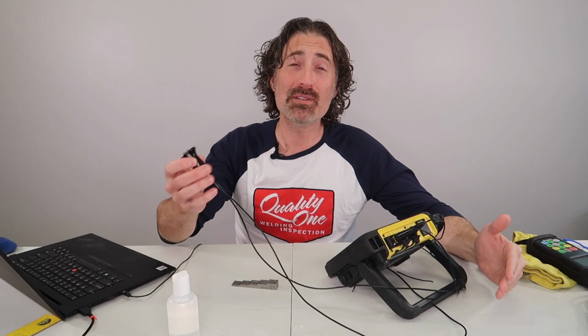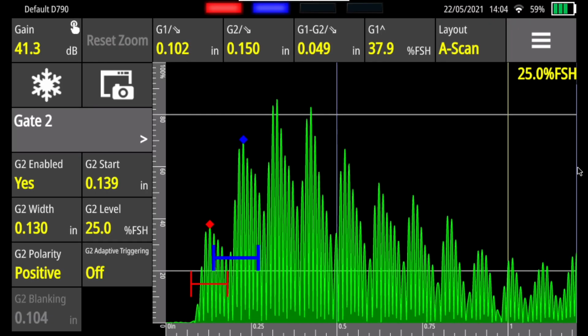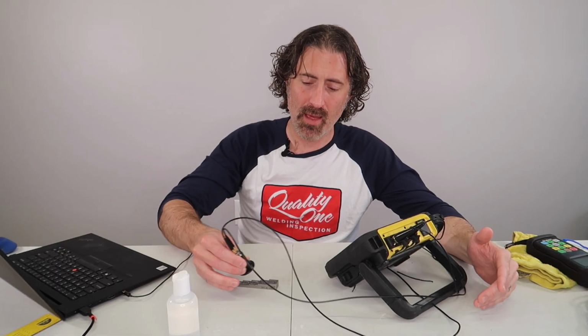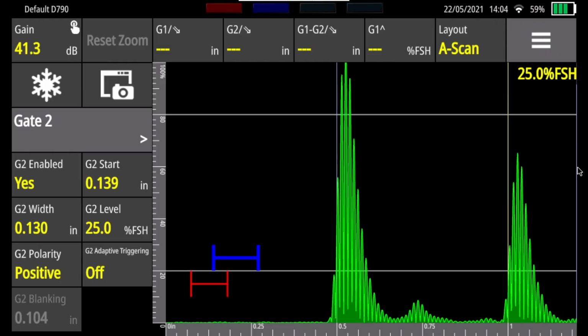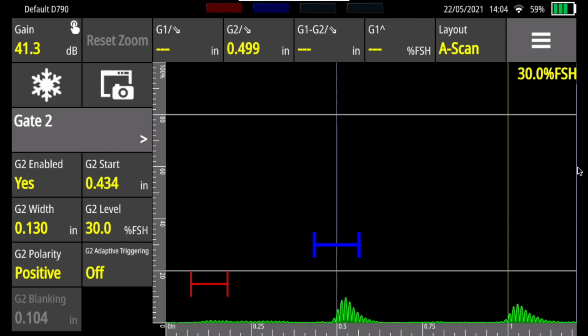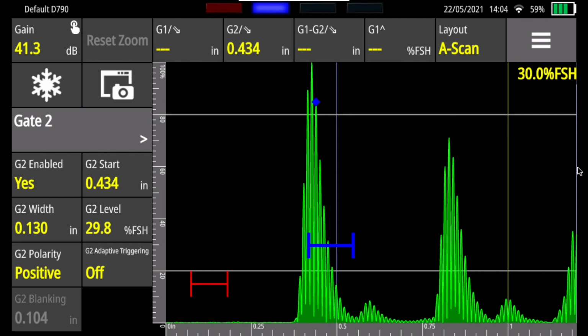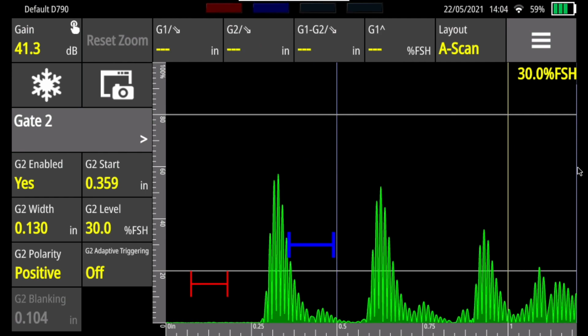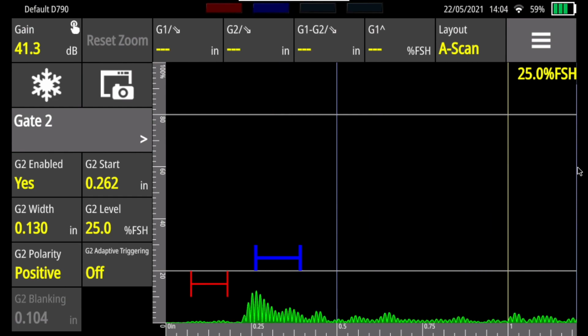Do we really have to worry about V-path error? Well, if you're using a D790, probably not. I'll show you an example here. We'll put it on the 0.1 inch end of the wedge. You can see gate 1 edge reads 102. I'm okay with that. We'll put it on the 0.5 inch end. We'll move gate 2 over there. I get 499. I'm okay with that too. Let's go to 400 and I get 400. We'll move to 300 and I get 300, and 200 and I get 200. So you can see a D790, nice and tall, low roof angle, pretty much no V-path error.